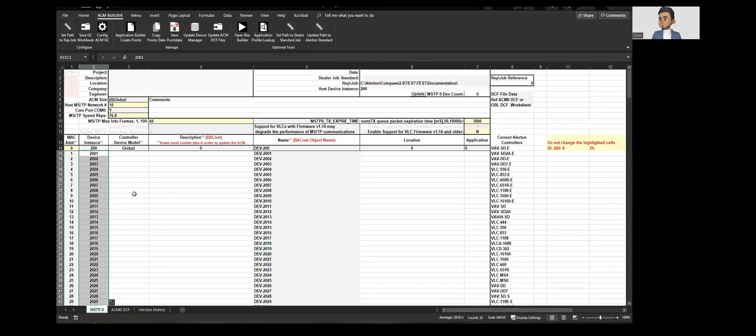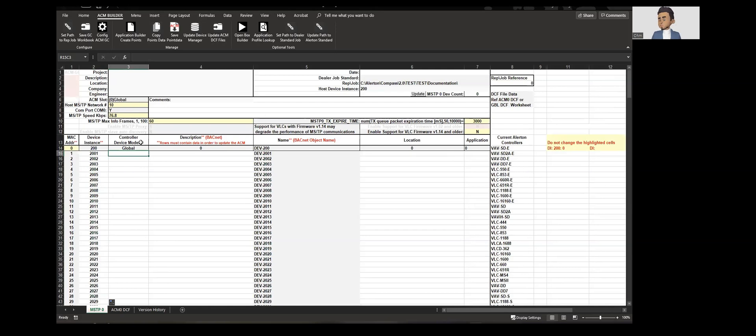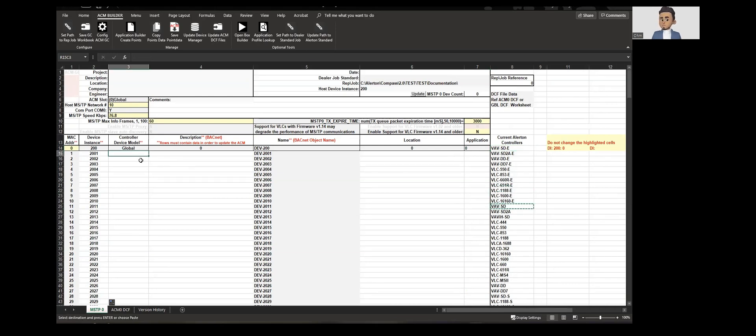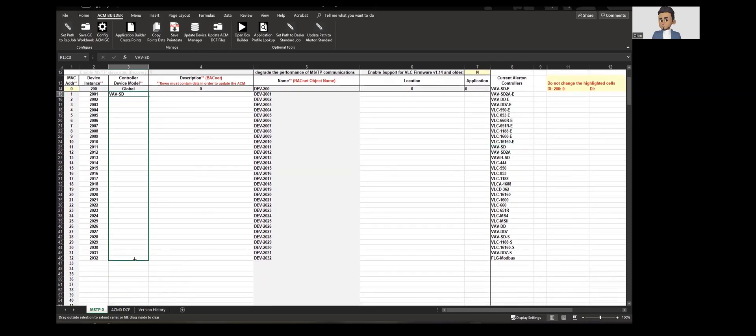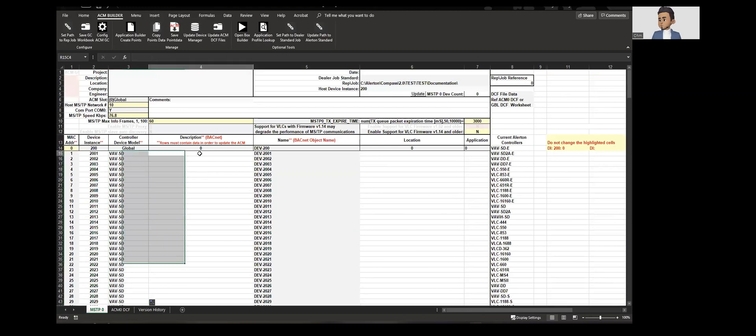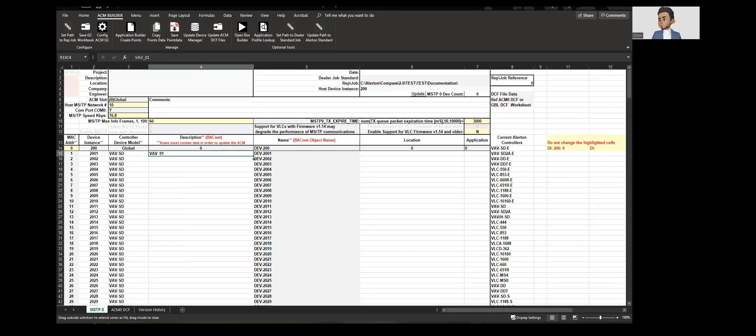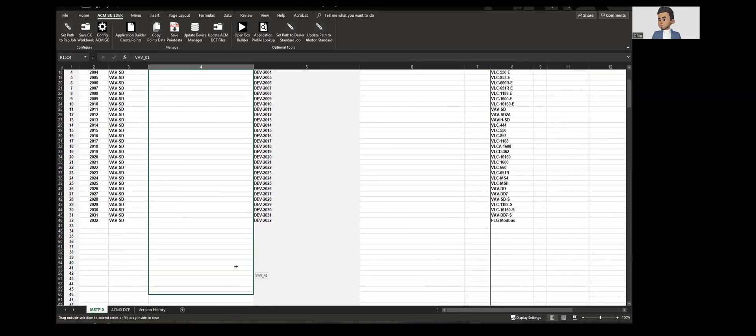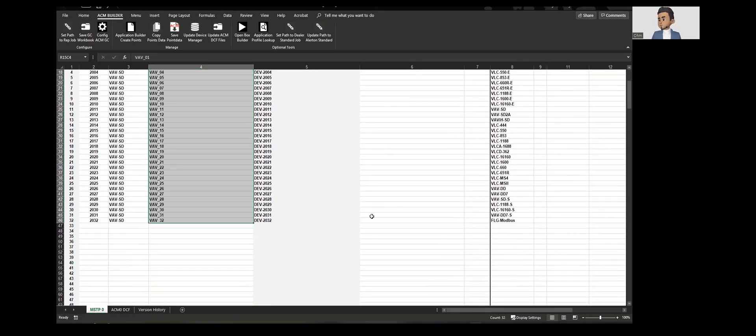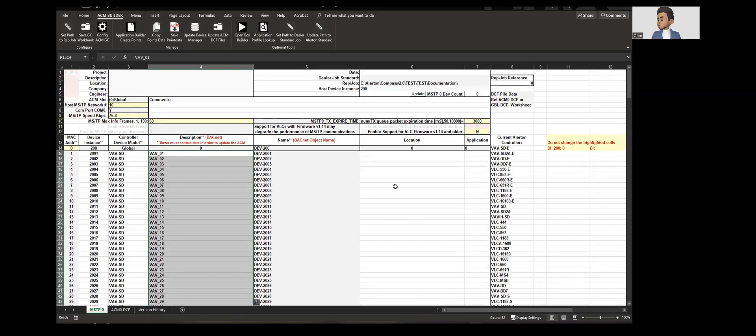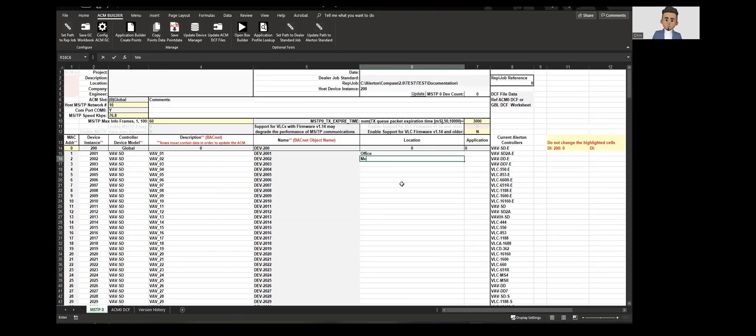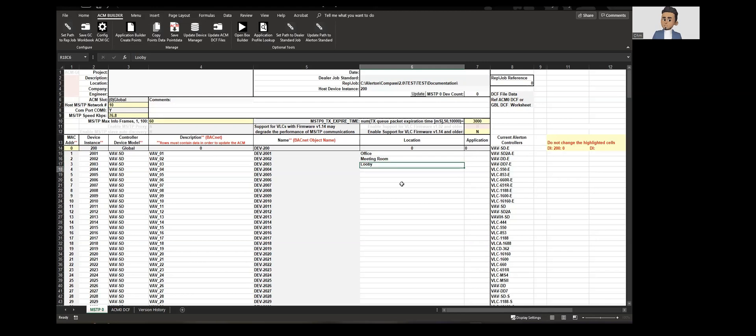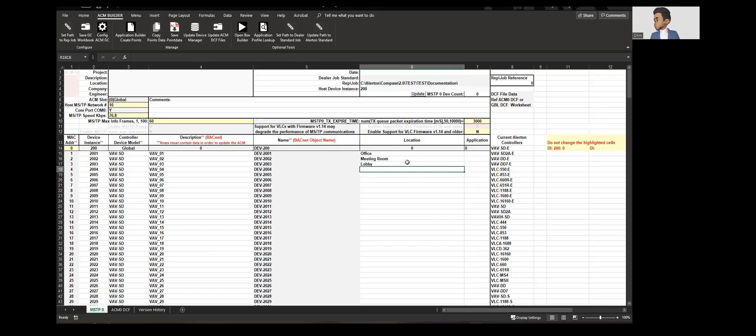32 devices are there. Now the device controller module, you can refer column 8 for that. For now I will consider VAVSD as my device model number. Description, let us call it as VAV_01. We have added description and this is the device object name. Let's leave it in the location. You could add like office, then meeting room, then maybe lobby, etc.